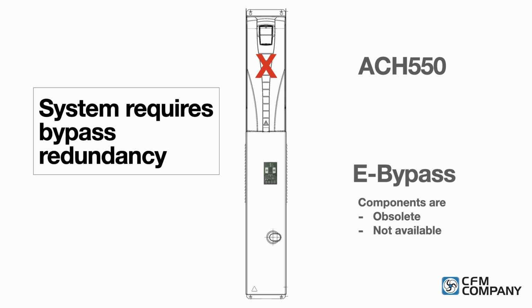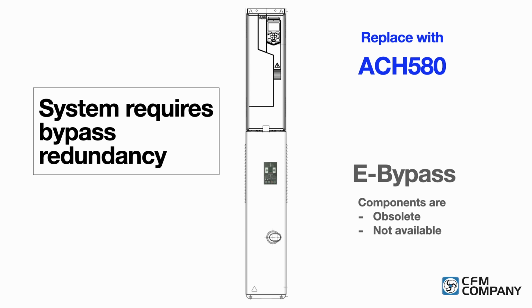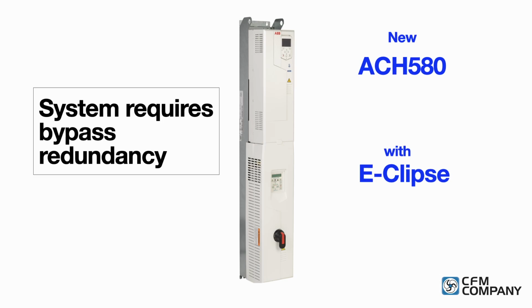The problem with using the original bypass is that a customer could replace the damaged drive with a new ACH580 drive and then quite possibly a week later have a component of the original electronic bypass fail. This would cause an additional outage. To achieve the redundancy goals required by the system and to avoid a future failure of the original electronic bypass, the customer will need to replace the entire enclosure with a new ACH580 drive and E-Clipse bypass.